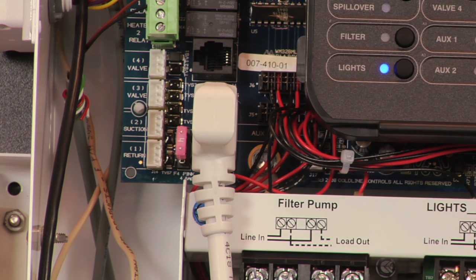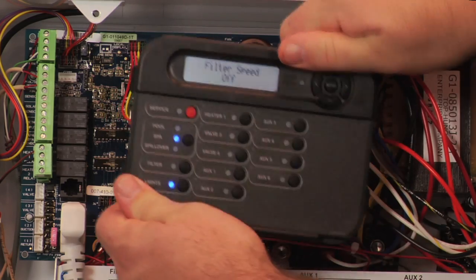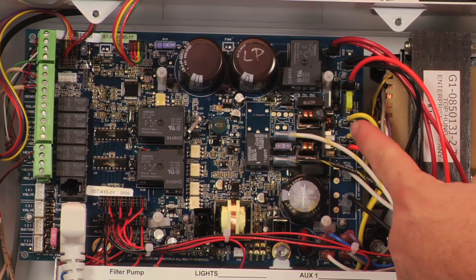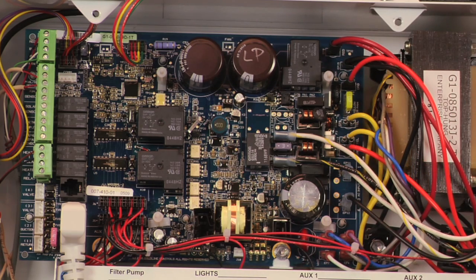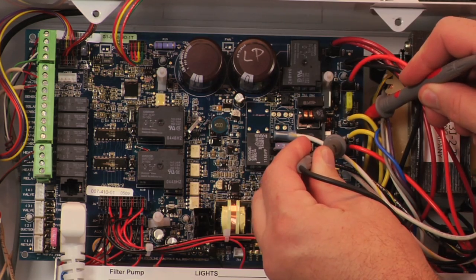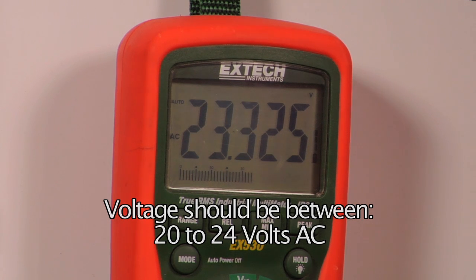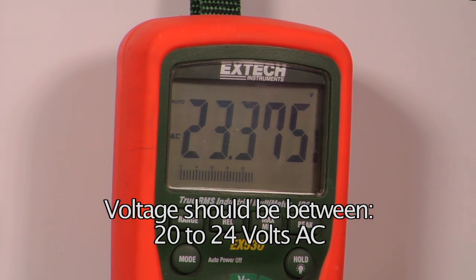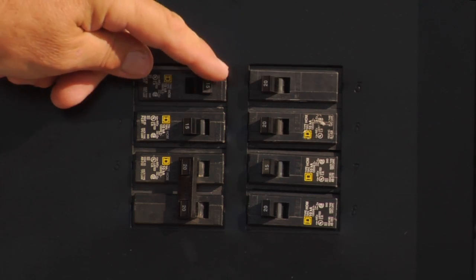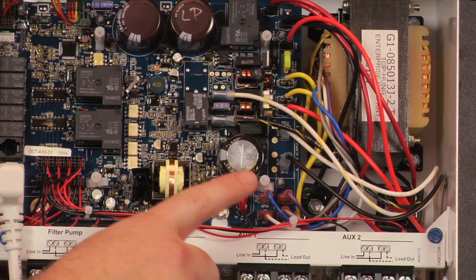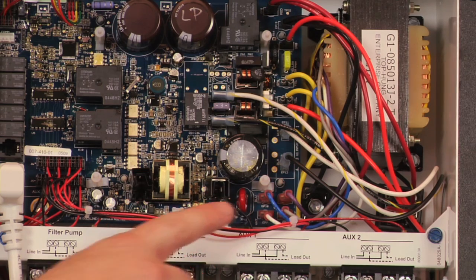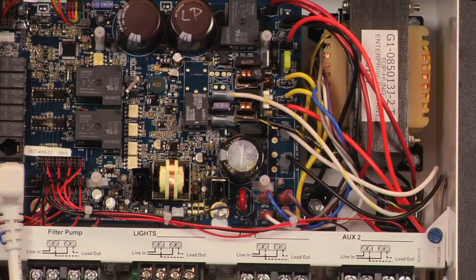If the turbo cell is plugged in, remove the local display. Measure the voltage between the yellow terminals on the main board. The voltage should be 20 to 24 volts AC. If the voltage is not present, shut off power to the control box, disconnect the blue and white wires located in the lower left corner from the main board.